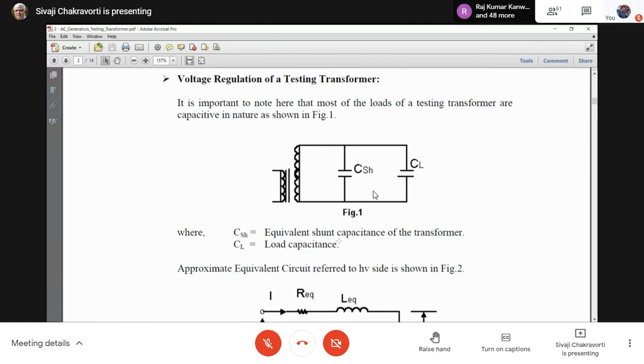voltage regulation of a testing transformer. So here is Figure 1, the testing transformer, the low voltage winding, the high voltage winding. Then CL is the equipment under test, the capacitance of that equipment. Then what is the CSH? This is called the stray capacitance between the high voltage line and earth, which you cannot avoid. It is always there. Don't ignore it.